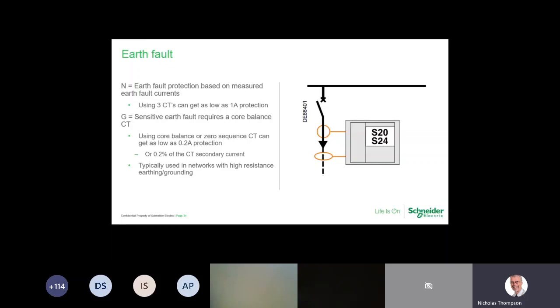One kind of application that springs to mind is quarries, where you don't have a lot of earth, you have a lot of rock, and you then get a lot of problems with earthing. Areas of the country which do suffer from this are like Cornwall. There are areas in Cornwall where WPD use sensitive earth fault protection and detection. Up in Scotland, in the mountainous areas, or Wales, that can also be a problem. Quarries, it did used to be part of the Mines and Quarries Act. One of the DNO protection engineers said the quarries tend to throw the sensitive earth fault protection back at them. So it very much seems to be that kind of thing.